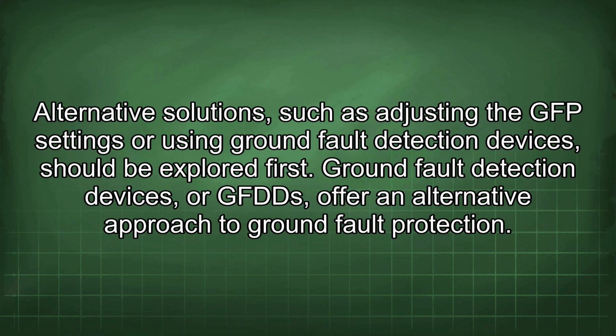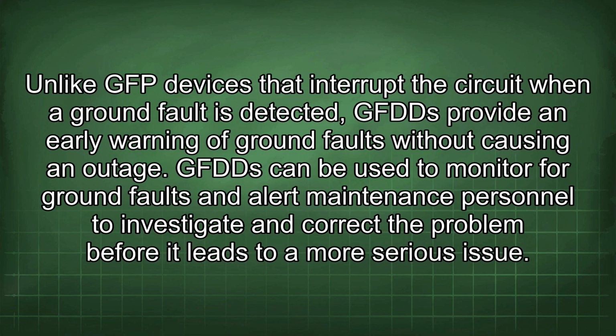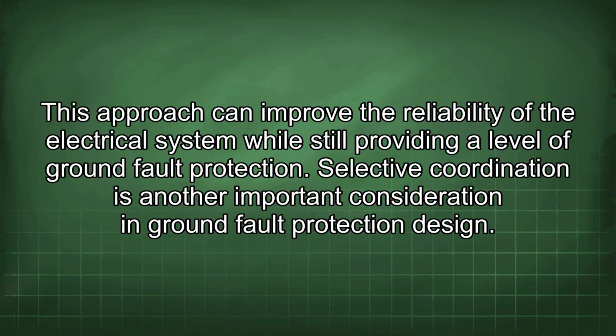Ground fault detection devices, or GFDDs, offer an alternative approach to ground fault protection. Unlike GFP devices that interrupt the circuit where a ground fault is detected, GFDDs provide an early warning of ground faults without causing an outage. GFDDs can be used to monitor for ground faults and alert maintenance personnel to investigate and correct the problem before it leads to a more serious issue. This approach can improve the reliability of the electrical system while still providing a level of ground fault protection.